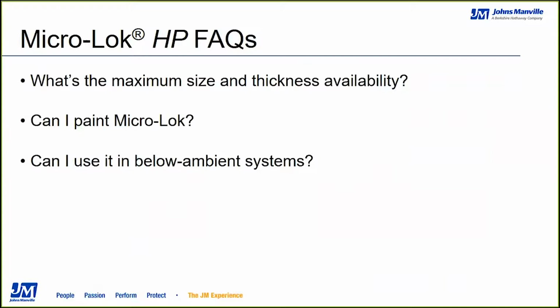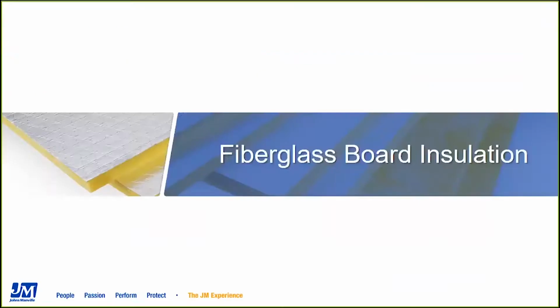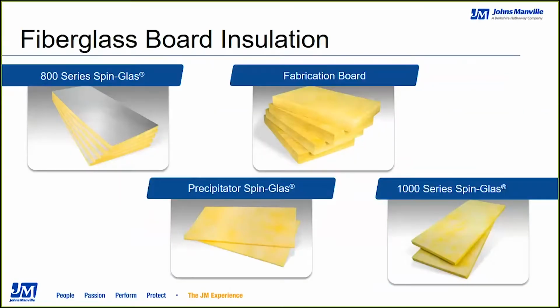Ultimately, this is not for products below zero or systems running below zero, as there are better closed cell options for those types of systems. But anything between 0 and 450 degrees as an operating temperature is acceptable. Fiberglass boards.